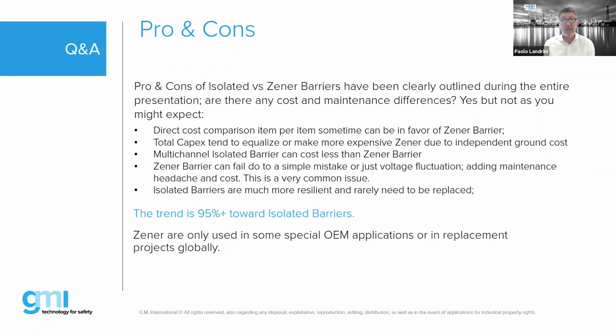Another point in the pros and cons is the headache typically associated with Zener barriers: any voltage fluctuation, even a simple mistake like shorting the wire, will cause a Zener to blow, because that's what they're designed for. And blowing means replacement. An isolated barrier is inherently much more resilient—you can short the wire, you can reverse the wire, and you need a lot of voltage before you blow a fuse in an isolated barrier, you have to go above 250 volts. So they are inherently more resilient, giving you less problem in maintenance.